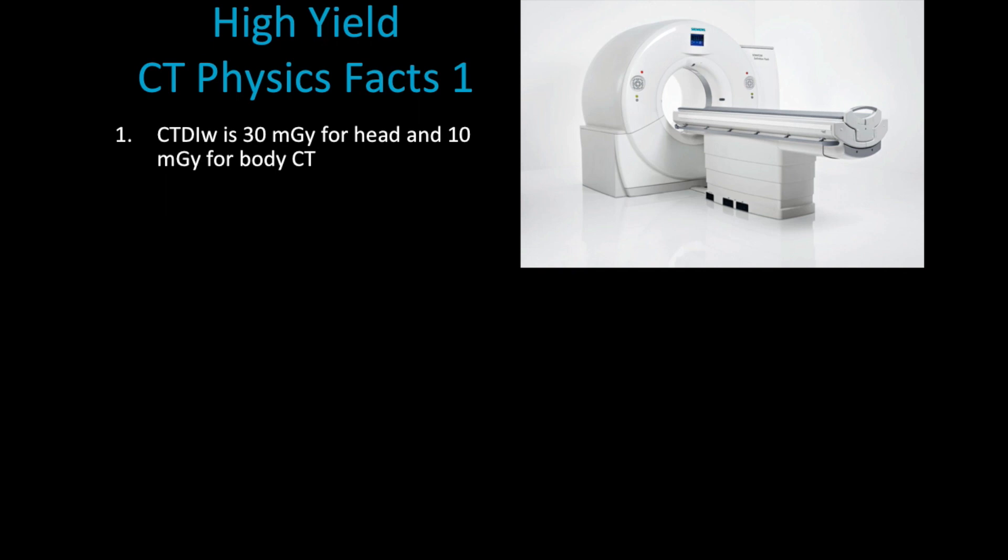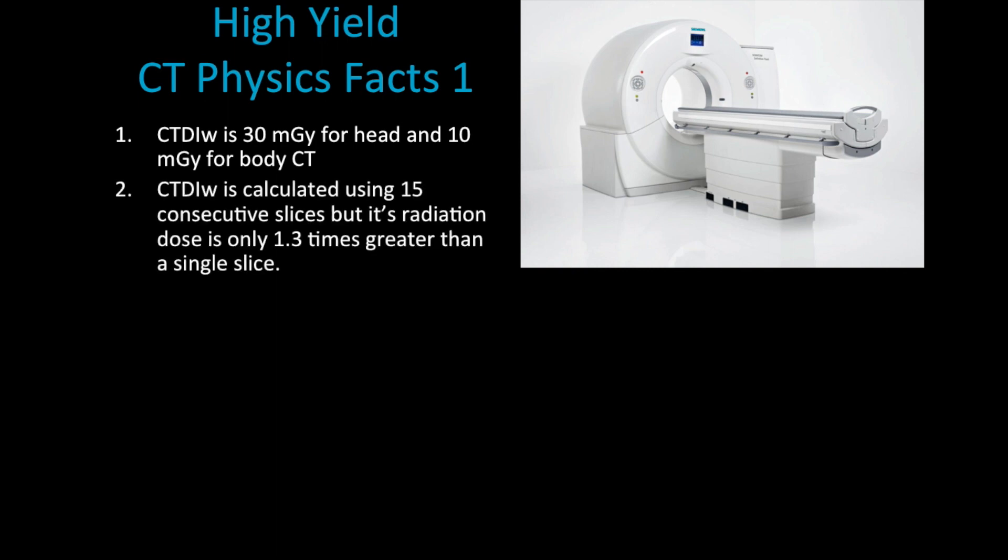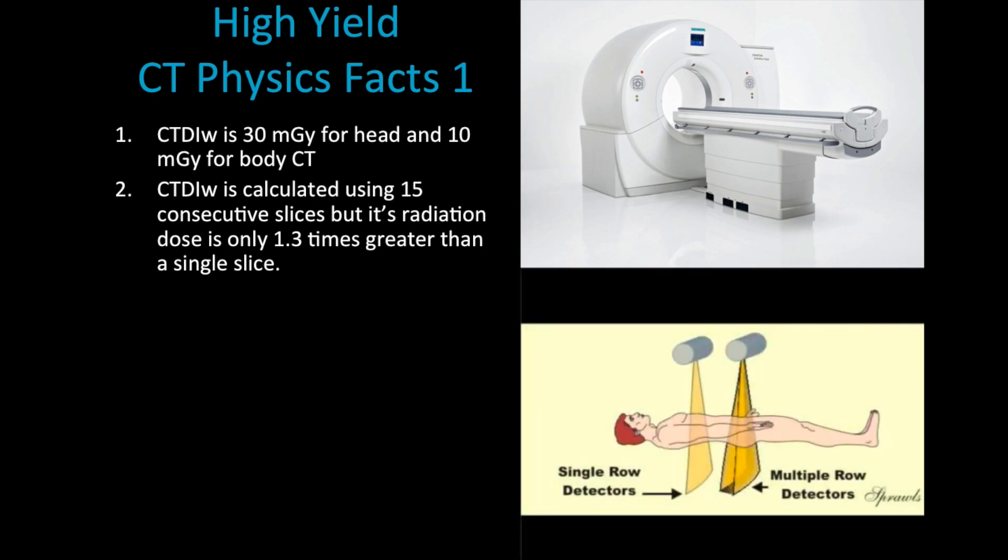The calculation for CTDI depends on 15 consecutive slices, but it also takes into account the radiation that occurs as scattered radiation at the two edges of the x-ray beam. They're also called the two tails of the x-ray beam, in which they have scattered radiation.